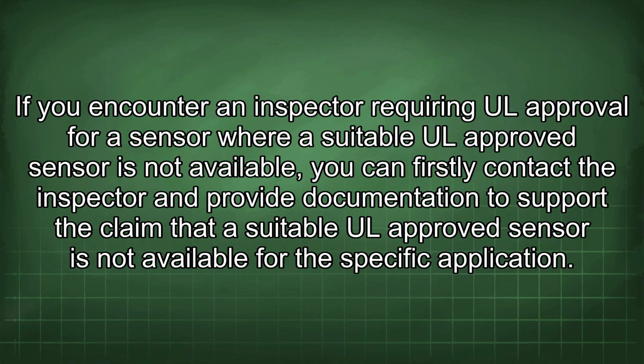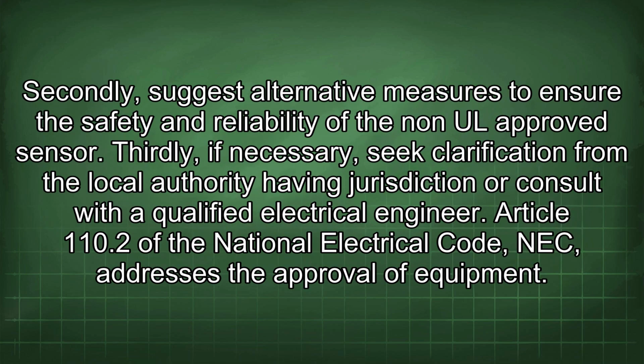If you encounter an inspector requiring UL approval for a sensor where a suitable UL-approved sensor is not available, you can firstly contact the inspector and provide documentation to support the claim that a suitable UL-approved sensor is not available for the specific application. Secondly, suggest alternative measures to ensure the safety and reliability of the non-UL-approved sensor. Thirdly, if necessary, seek clarification from the local authority having jurisdiction or consult with a qualified electrical engineer.